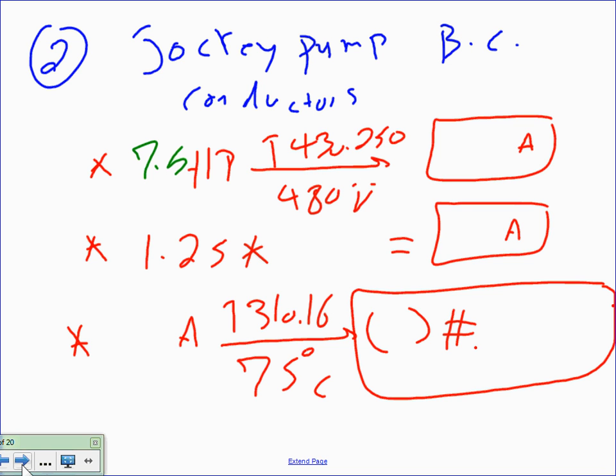Okay, the second one, we're going to go to the Jockey Pump. The Jockey Pump, guys, piece of cake. You have 7.5 horsepower. Take it to the same table. You're going to get 11 amps, Chris, right? That's in your calculator. You take the 11 amps and multiply by 1.25, which gets you 14 amps. And if you get the 14 amps, what do you think you're going to get? 3 conductors, and what size each one of them? Number 12, RHW. Done.